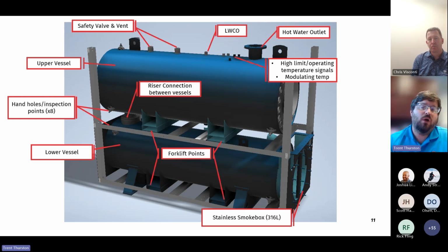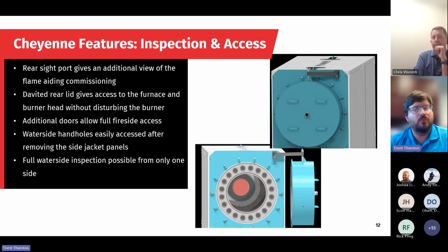Our standard way of shipping this is to have it fully jacketed, fully assembled, with the temperature controls and low water cutoff fully factory wired and mounted. The only field hookups that you should need would be the outlet and return connections, and then your safety valves and vents. One of the final things I'd like to point out on this is we do have these handholes and inspection points on each side, which will come in handy on this next one, talking about our inspection.